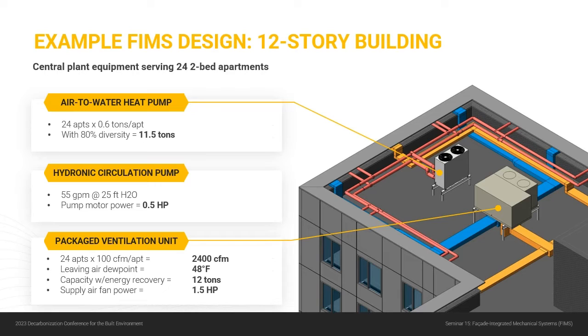Now let's look at the equipment that's going to go up on the roof for this wing of the building. I mentioned before, each apartment is roughly 0.6 tons. We're serving 24 apartments. That's 2 apartments per floor. And so we get to apply some diversity to that. We end up with a roughly 12-ton heat pump to serve this wing of the building. And then the circulation pump circulating the water would be roughly half horsepower. So it's half horsepower to serve 24 apartments. So it's relatively low energy.